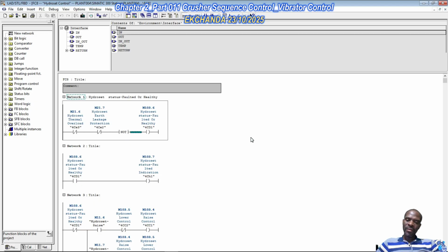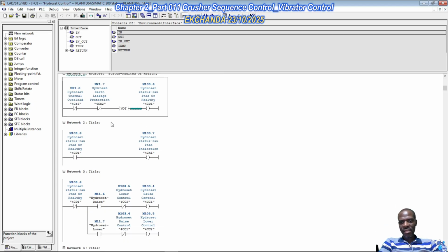because to validate our inputs, we said any change in transition of the inputs needed to be accepted, meaning if it transitions from false to true, it triggers a fault in the system. Then for you to normalize, you need to reset that input. Okay, so this wouldn't be necessary to seal in at this point. It would just latch. It wouldn't reset even if there was a transition in the defining inputs.